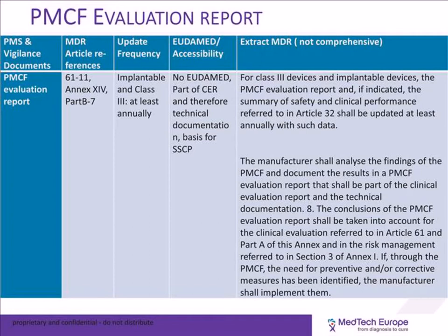It also will be the basis of the summary of safety and performance. For implantable and class 3, these reports need to be updated at least annually. So the "at least" is not defined in the regulation, but need to be clarified by procedure in terms of threshold for revision.